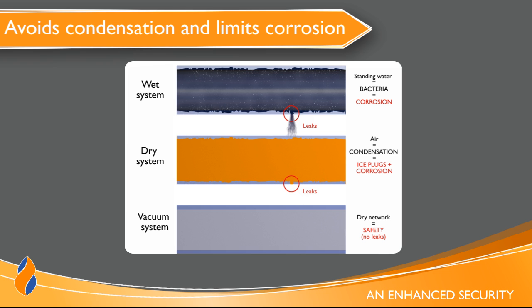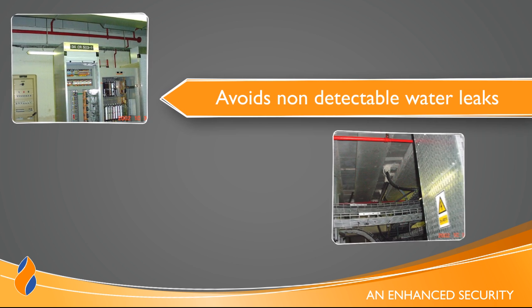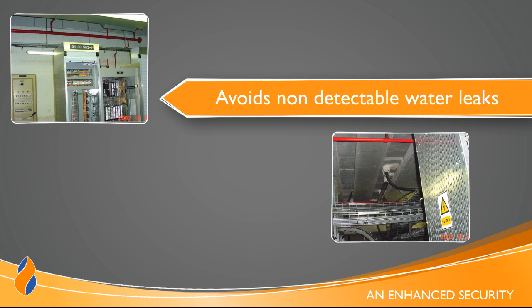In a vacuum system, air is dry and preserves pipes from corrosion and leaks. This makes the fire protection systems very reliable over time. The VACTEC system avoids non-detectable water leaks whose consequences can be catastrophic.